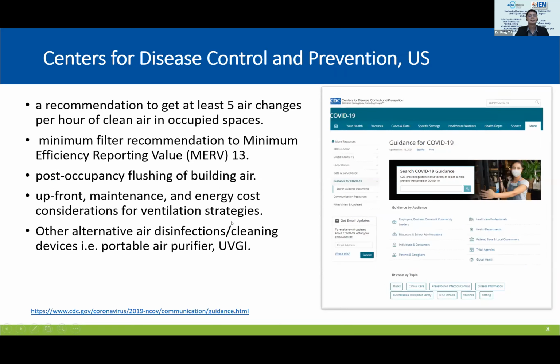The CDC recommends 5 ACH, 5 air changes per hour of clean air in the occupied space, and the minimum filter recommendation is MERV 13. For office buildings during a lockdown, when no people occupy the buildings for a long time, flushing the building air is recommended. If possible, during the peak times of COVID-19, there is also a recommendation to flush the air in the buildings during the change of occupancy group. Other alternative air disinfection or cleaning devices can be applied, like portable air purifiers or even UVGI.